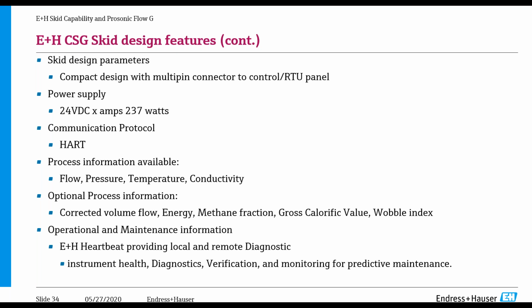As I mentioned, you can do corrected flow on the G300 as opposed to doing the correction inside an RTU or control system. There's an energy measurement, there's a methane fraction measurement, calorific value, and Wobbe index.